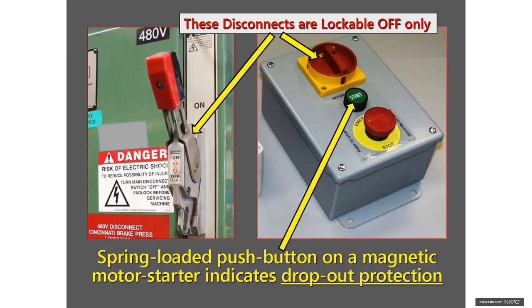As far as the starters are concerned, you see the one in the center on the right-hand side? That's a spring-loaded push button. That's how you know if you have a magnetic motor starter or not, a spring-loaded push button. Of course, the ring around it protects it from unintended operation.